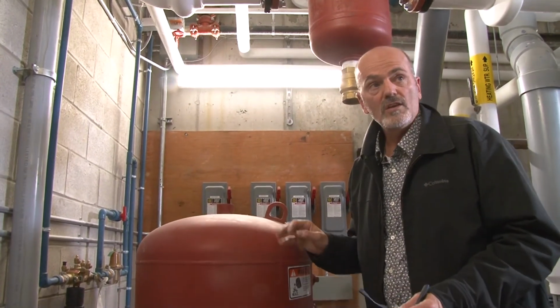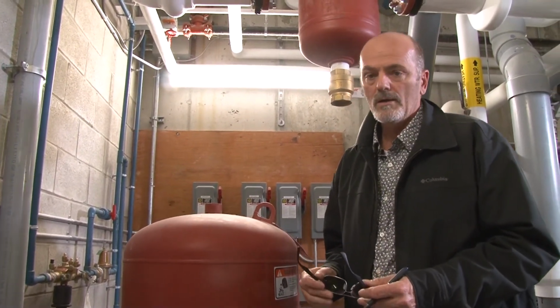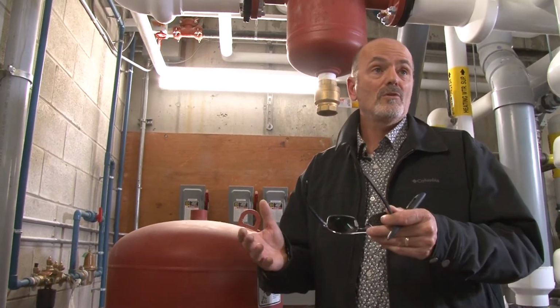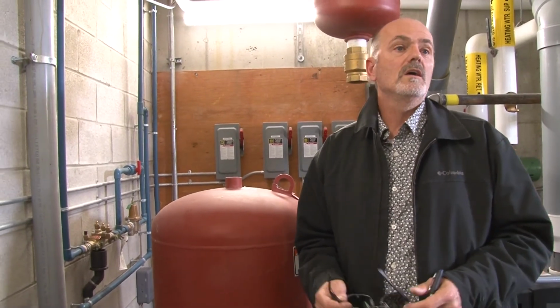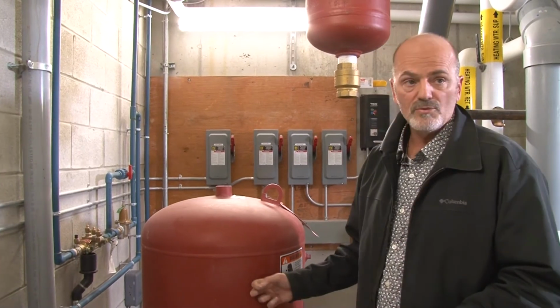So you'll start to see situations where the boiler PRVs could start blowing off because there's no place for the water to go. There's no place for the water to expand. So it starts blowing off on pressure reliefs elsewhere. And that's an indicator that you have a rupture in your bladder.